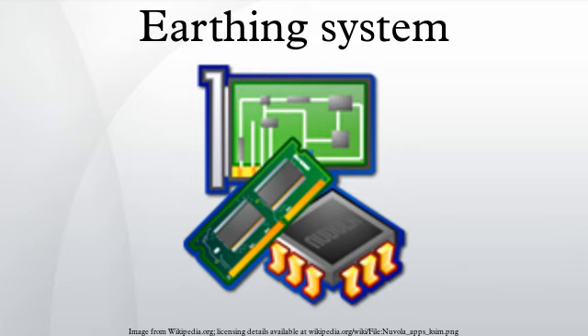TN-C, where a combined PEN conductor fulfills the functions of both a PE and an N conductor, is rarely used. TN-C-S, where part of the system uses a combined PEN conductor, which is at some point split up into separate PE and N lines. The combined PEN conductor typically occurs between the substation and the entry point into the building, and is separated in the service head.